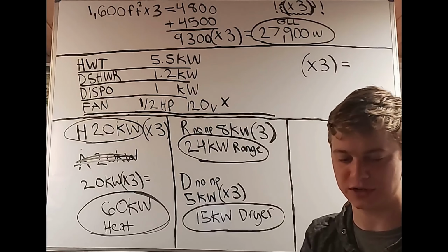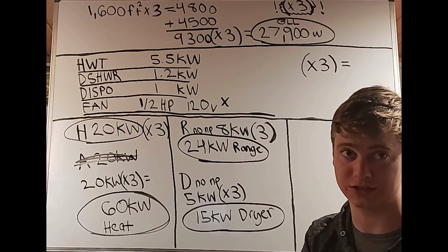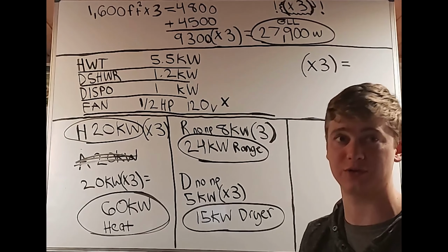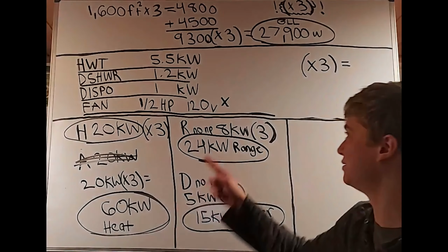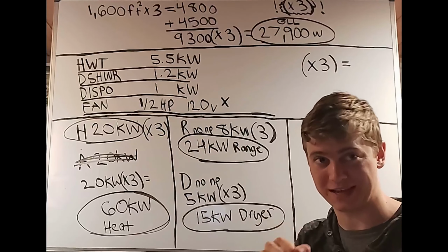So in the table here, we see 115 volts, but we need to know when we do our load calculations, we're only using nominal voltages. So although we're going to look under the 115 volt column, we're going to use 120 volts for load calculations because that's what it tells us to do.